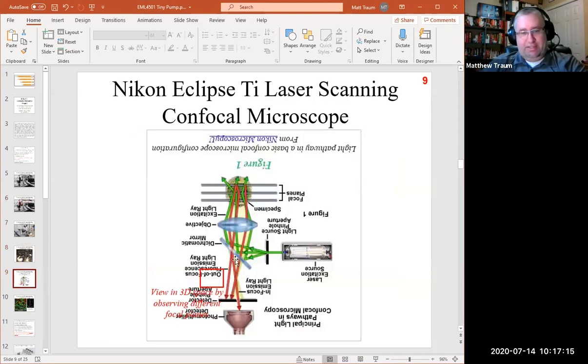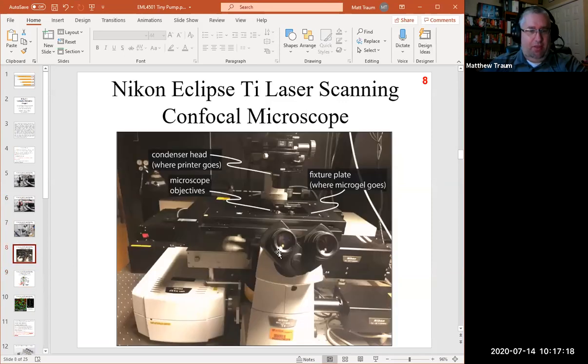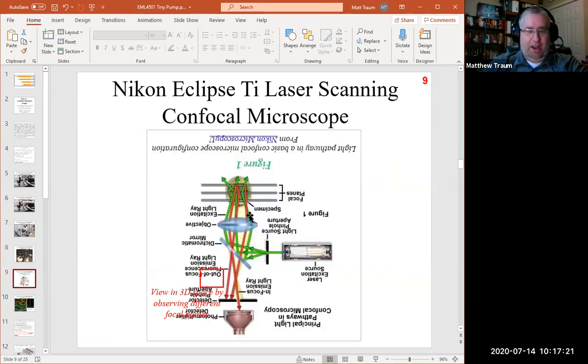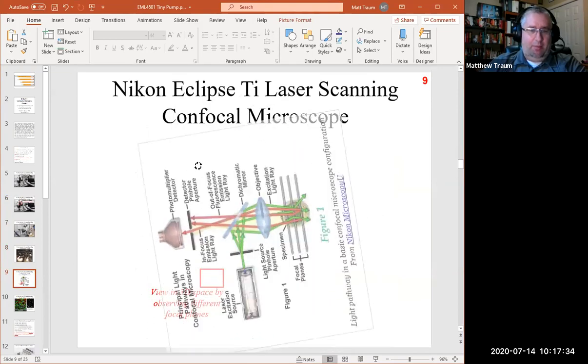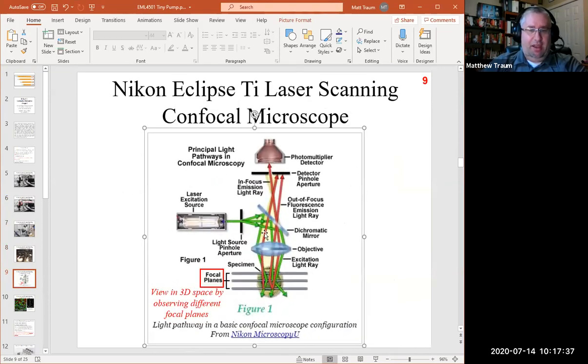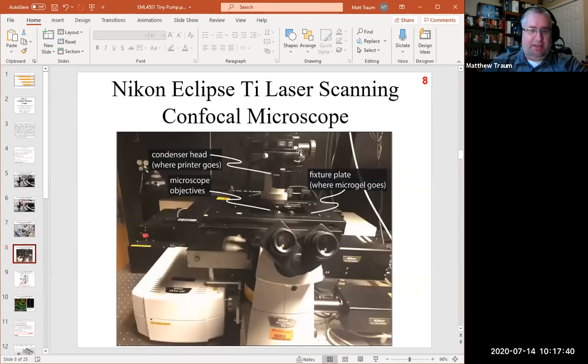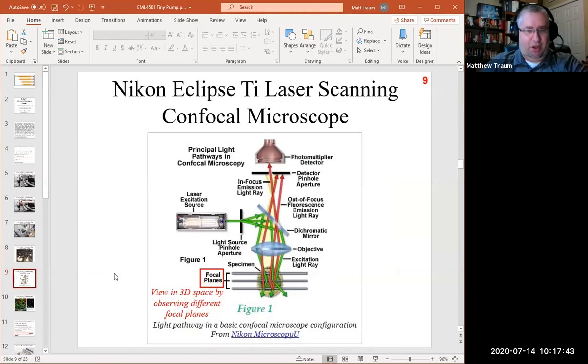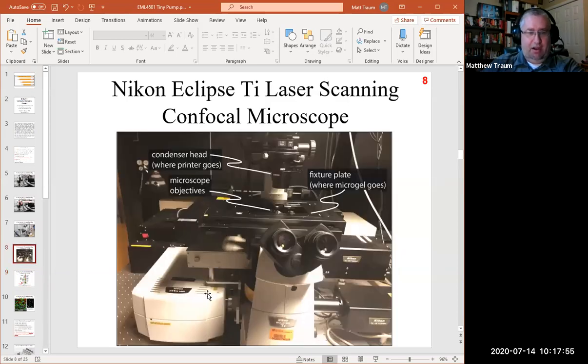I've intentionally flipped this image over so that the arrangement of the microscope aligns with the arrangement of the figure, but of course it's hard to read upside down, so let me flip it back over. The point I want to make is that this image might be a little confusing because it's flipped over in terms of its orientation with respect to how the optics are aligned with the actual microscope. In general, the way a confocal microscope works is that there's a laser excitation source, and by the way, the laser is sitting down here, underneath the stage of the confocal microscope.